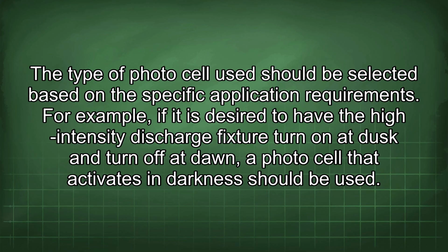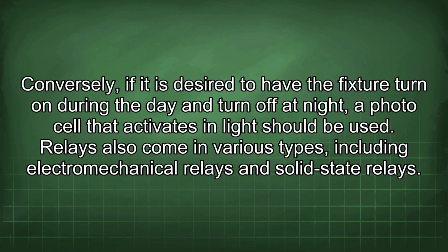For example, if it is desired to have the high-intensity discharge fixture turn on at dusk and turn off at dawn, a photocell that activates in darkness should be used. Conversely, if it is desired to have the fixture turn on during the day and turn off at night, a photocell that activates in light should be used.